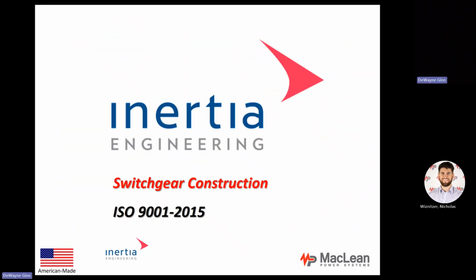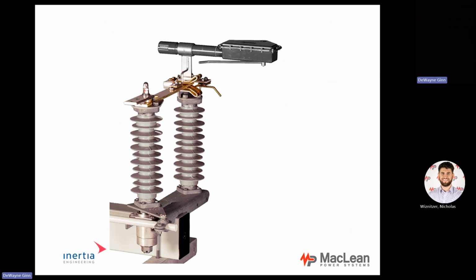Here's a switchgear construction. This is what I was talking about earlier. This is a phase unit, a single phase unit. If we look here, we can see, my arrow will not show you this, there's an interrupter on top of it that is on the very top. That's called an expulsion interrupter, and we'll talk a little bit about that as well. The blade is in the jaws, reverse loop contact jaws. We'll talk about that as well. At the bottom of this insulator on the left, there's a double seal stainless steel ball bearing. That's a cross arm. So we're just seeing one phase unit right here.